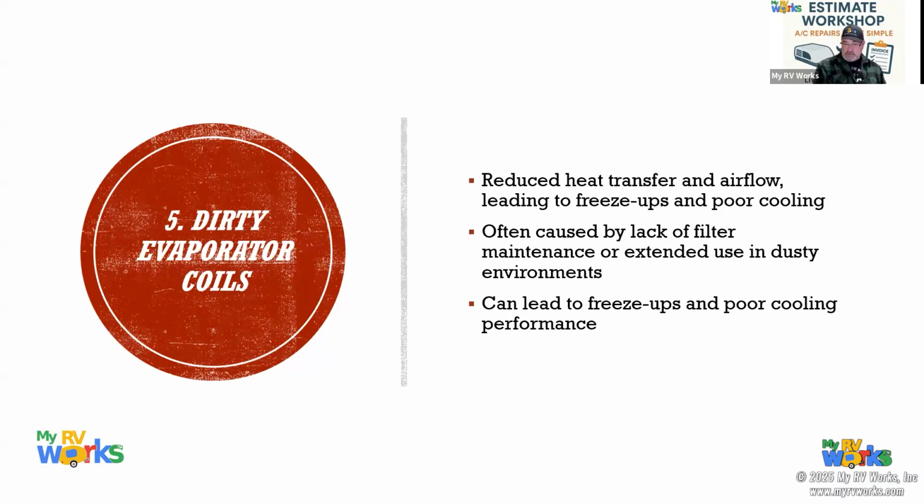Number five, dirty evaporator coils. And I've got the most incredible picture of one that is so full and so clogged, you don't even know what it is. And then I have another picture of me cleaning half of it and the other half dirty. But we all know you've got to clean these evaporator coils. All the dirt, dander, dust that's in the RV that's getting sucked into the air conditioner has to go through that, and they get clogged. It's supposed to be cleaned every year.